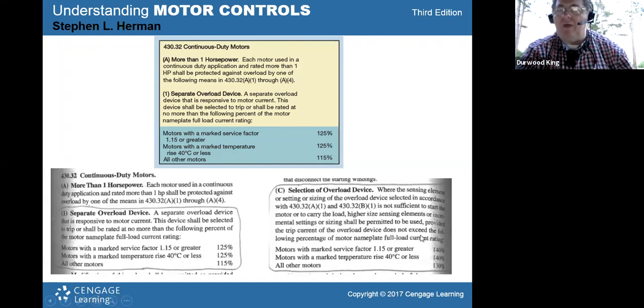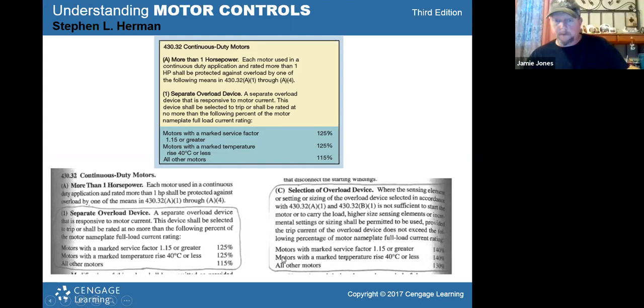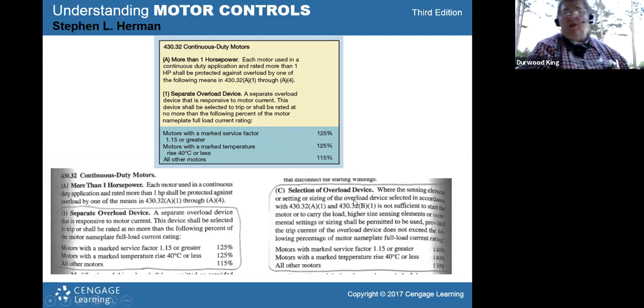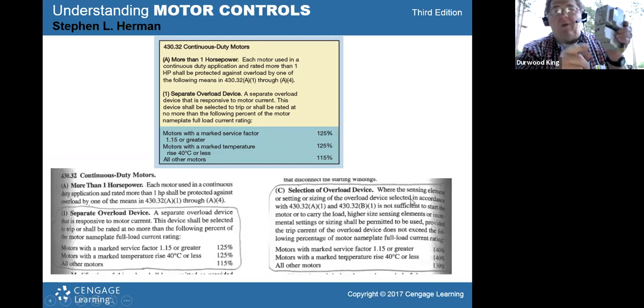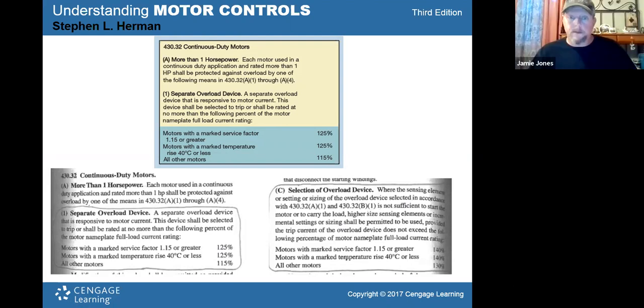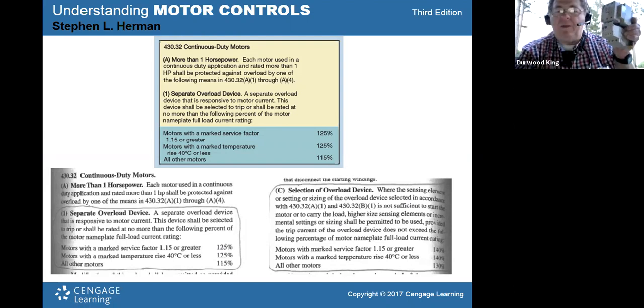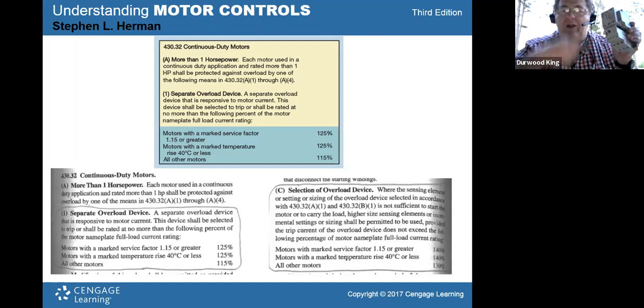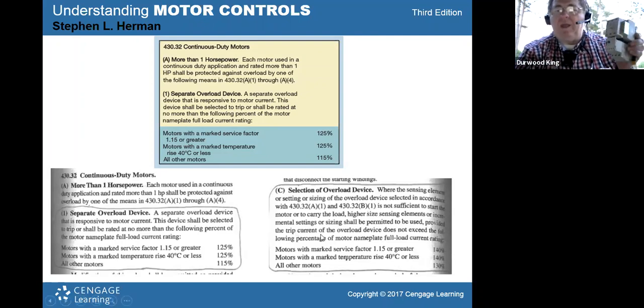You see over here on the right side of the screen where it says 140%? You see right over here? That says 140. This says 125. So it says in the code book that if you set that starter and you have a flywheel press or something like that, those big old punch presses, it takes them maybe 20 or 30 seconds to get up to top speed. Let's say you've got a punch press and that motor is belt driven, and it takes it 30 seconds to get up to top speed. And guess what? It's probably going to trip out if you set it for that before it ever hits top speed. So you're allowed to come over here to 140%.